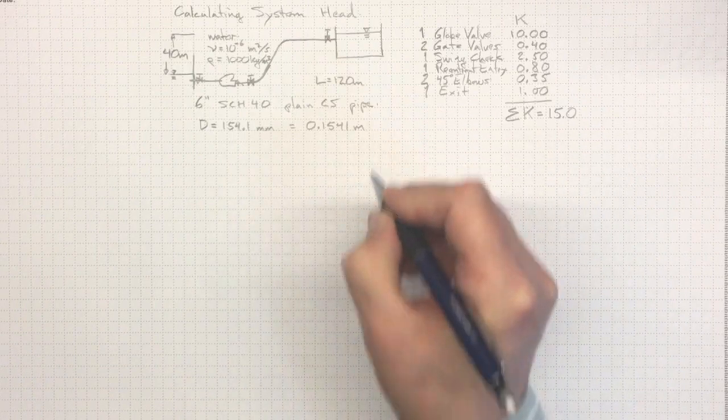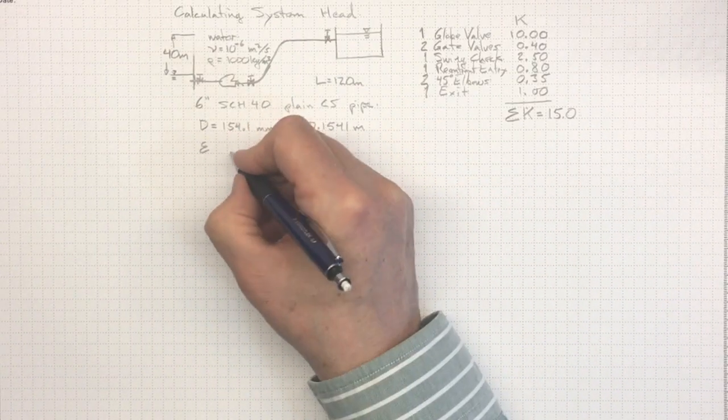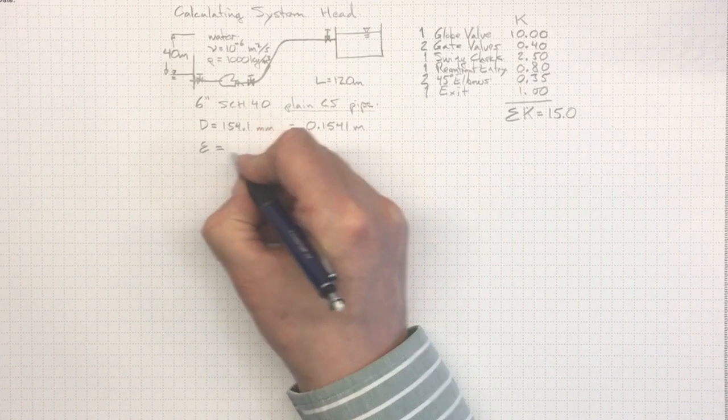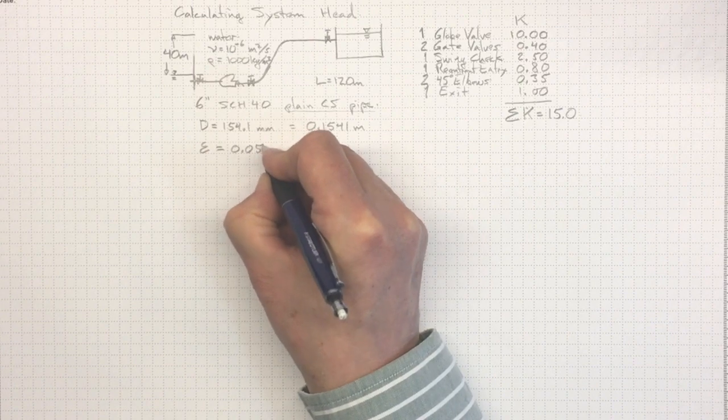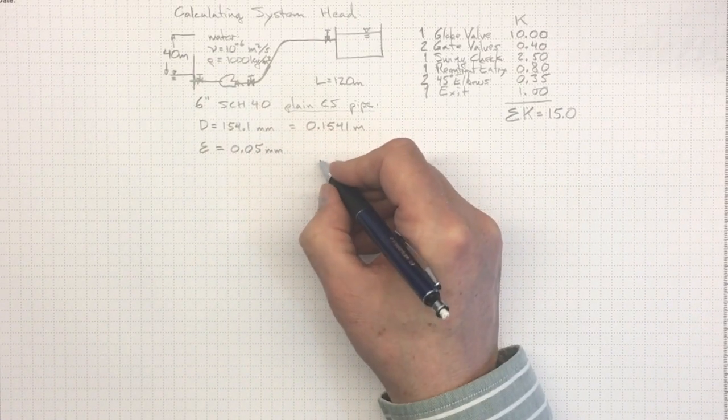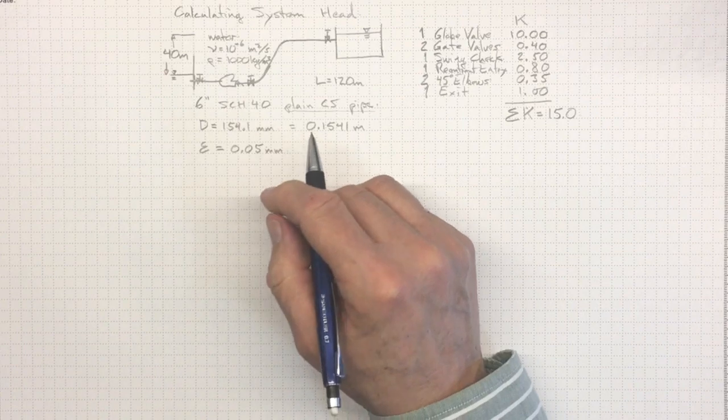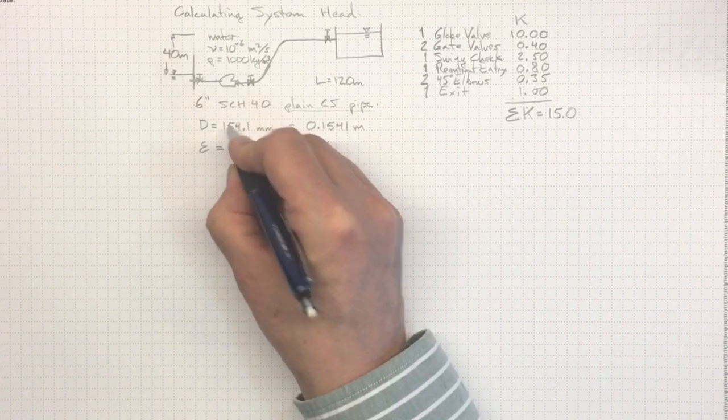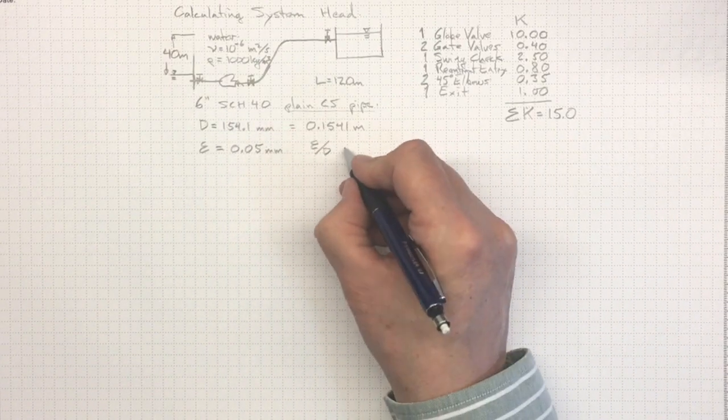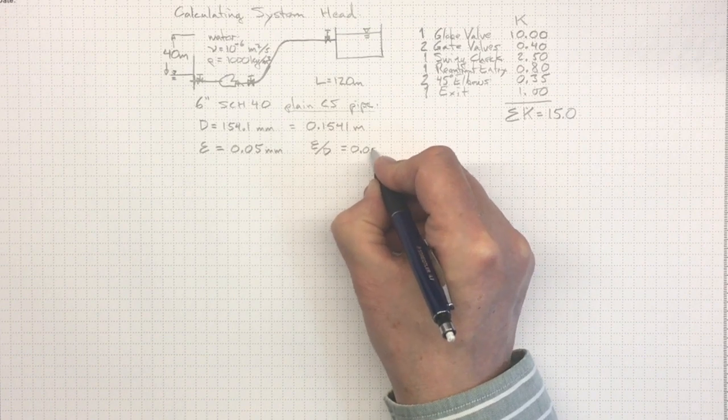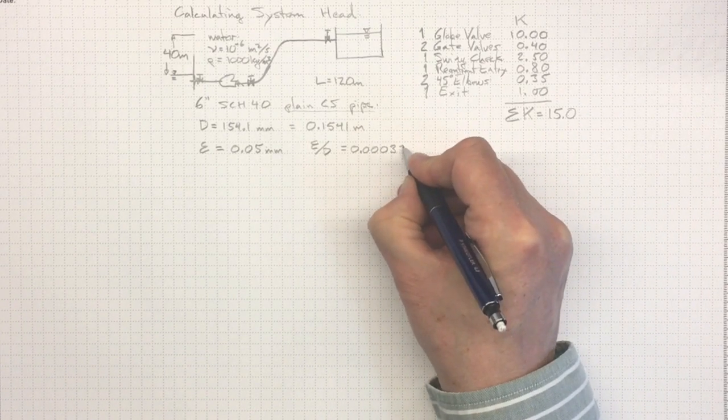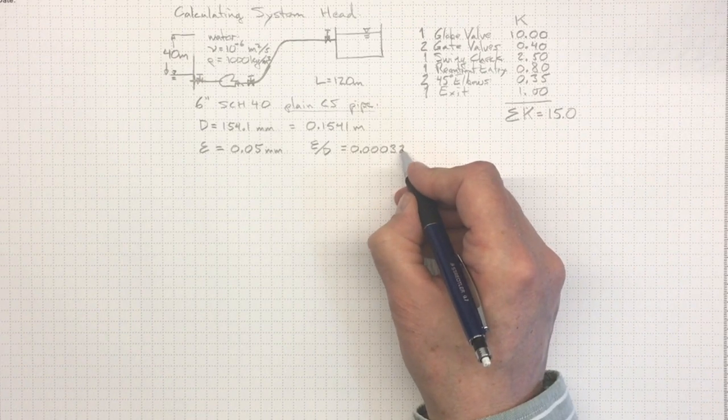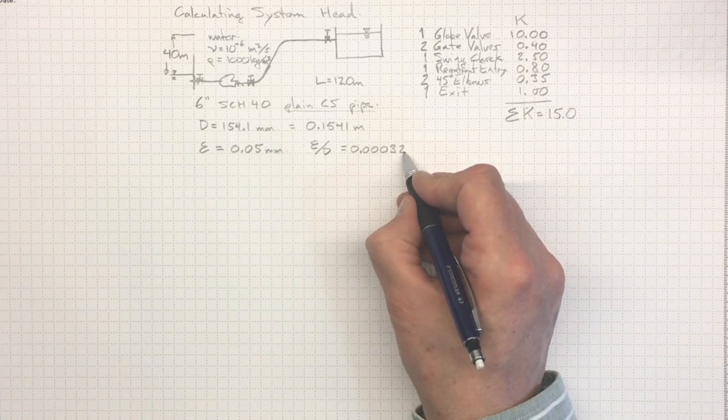The roughness for a plain carbon steel pipe will be something around 0.05 millimeters, so about 1/20th of a millimeter, quite a smooth surface. So, from that, we can get the relative roughness. That is, how big is the roughness compared to the diameter of the pipe. And that will turn out to be 0.00032. So, three parts in 10,000 for the roughness height on the inside of the pipe. So, that's a pretty smooth pipe.